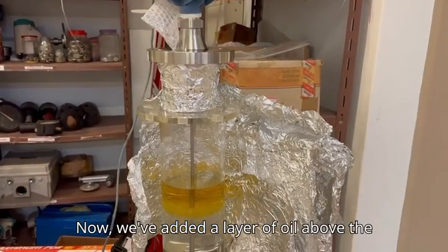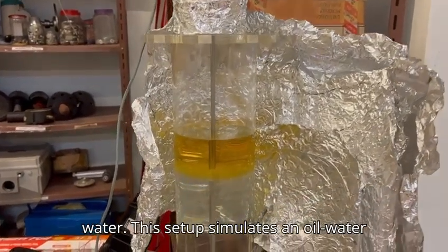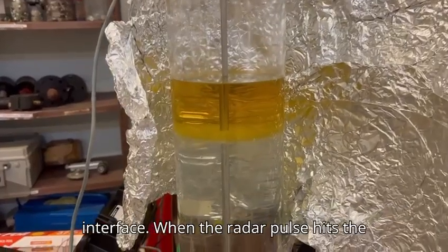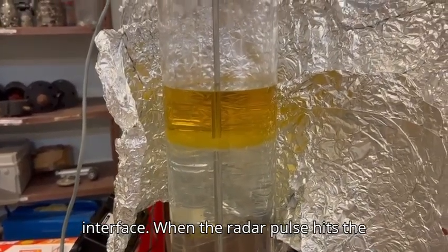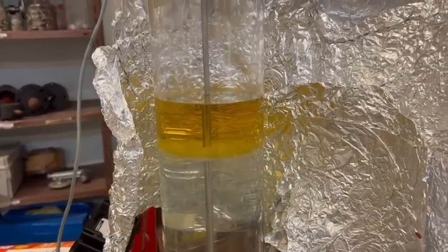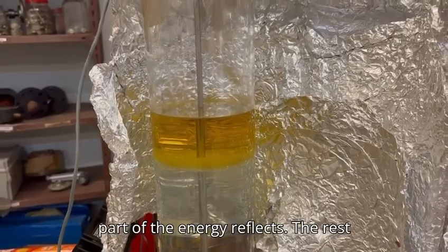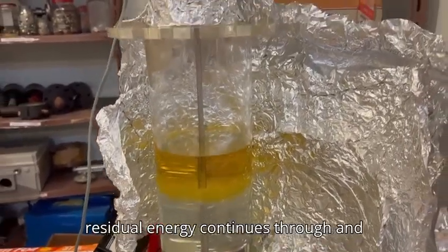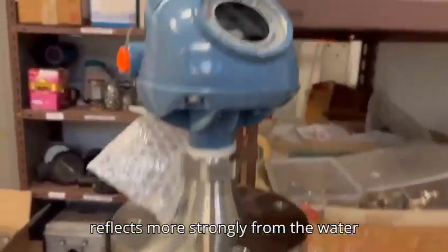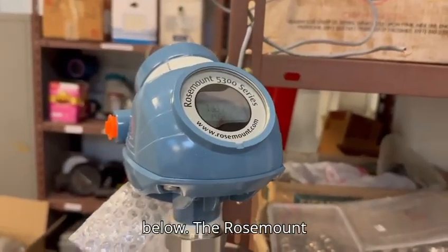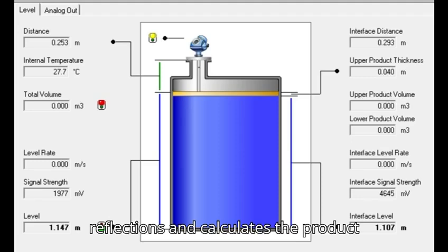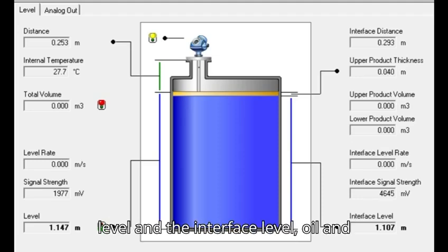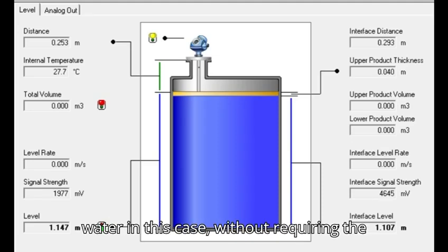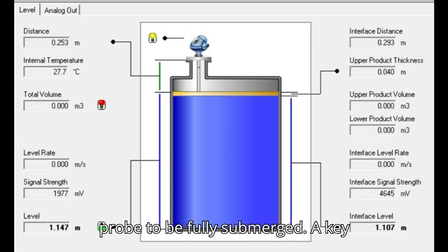Now, we've added a layer of oil above the water. This setup simulates an oil-water interface. When the radar pulse hits the oil with a lower dielectric constant, part of the energy reflects. The residual energy continues through and reflects more strongly from the water below. The Rosemount 5302 processes both reflections and calculates the product level and the interface level, oil and water in this case, without requiring the probe to be fully submerged. A key advantage of this model.